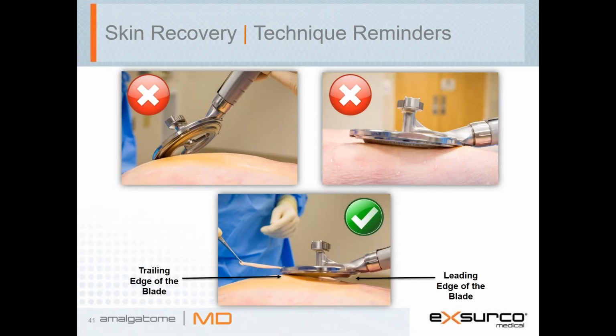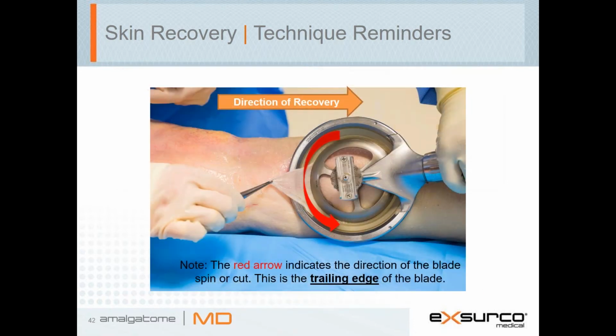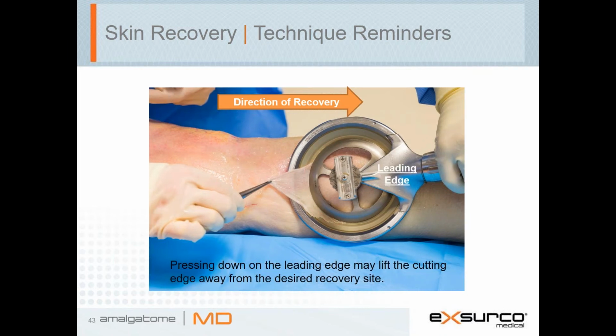There is a 15-degree angle built into the handle, so the operator does not need to hold the Amalgatome MD at an angle to recover a skin graft. Applying too much angle. Holding too flat. This is proper technique. The device cuts with the trailing edge of the blade. Pressing down on the leading edge may lift the cutting edge away from the desired recovery site.